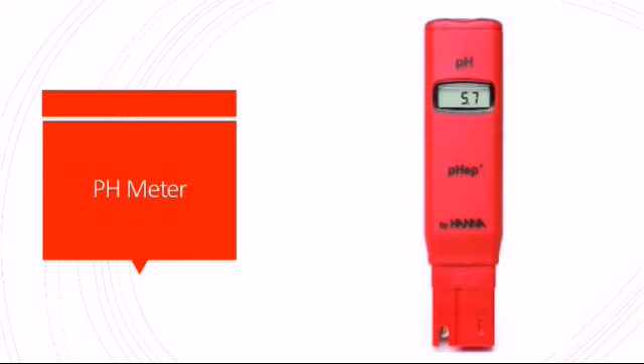pH meter. A pH meter is a scientific instrument that measures the hydrogen ion activity in water-based solutions, indicating its acidity or basicity expressed as pH. The pH meter measures the difference in electrical potential between a pH electrode and a reference electrode, and so the pH meter is sometimes referred to as a potentiometric pH meter. The difference in electrical potential relates to the acidity or pH of the solution. The pH meter is used in many applications ranging from laboratory experimentation to quality control.